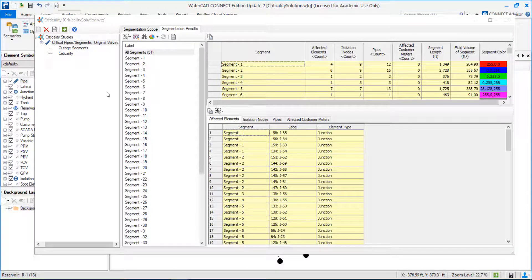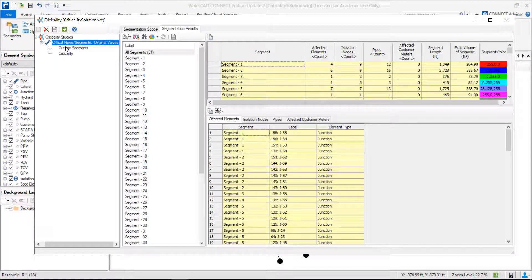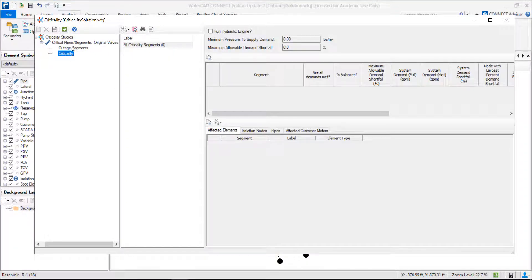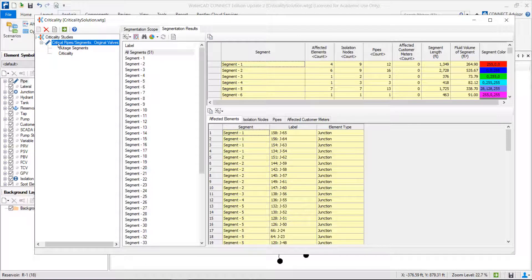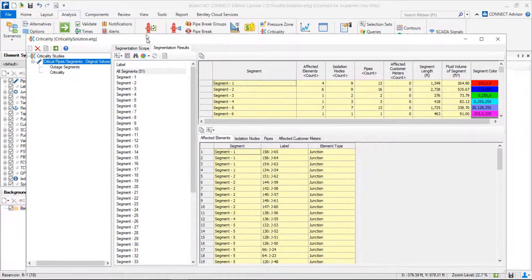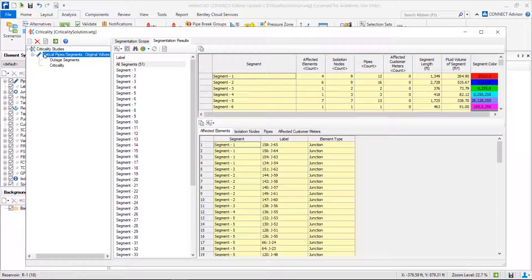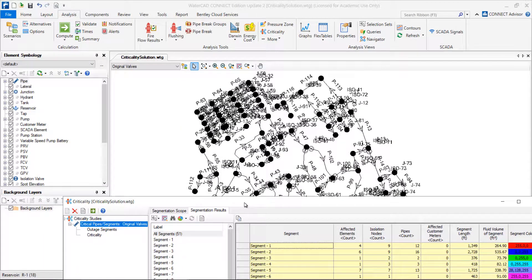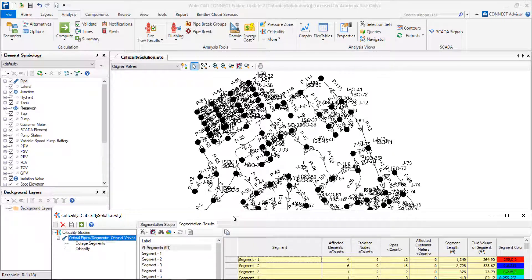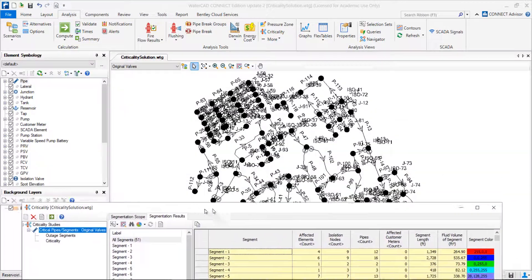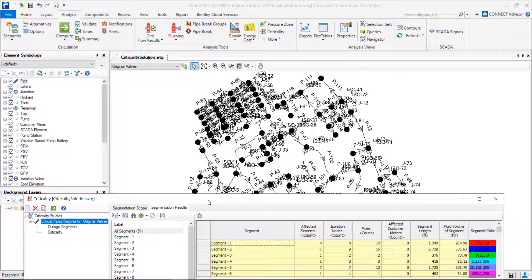In the criticality tool, we have three different results: one called critical pipe segments, another called outage segments, and another called criticality. Let's analyze first the critical pipe segments. Basically, in this part, we will have the identification of all our segments in our network. A segment, as we saw before, is the smallest isolable part of our network, and it depends on the valves we have around.